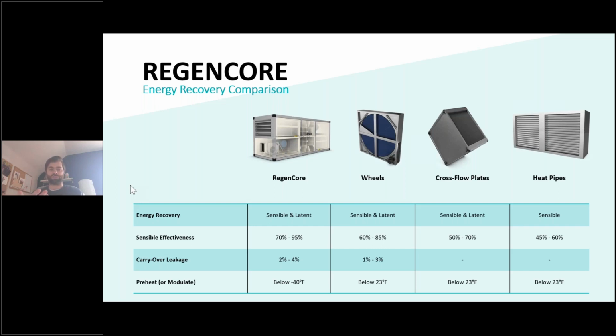One consideration with this type of technology, though, is the carryover leakage that you're going to have. So within the unit, when that damper swaps, any air from that damper section until outside is going to be brought back in and recirculated into your space. So if you have an indoor unit, that will include your duct section from that core all the way to the outside, but even with indoor units, it tends to be below 4% carryover leakage.